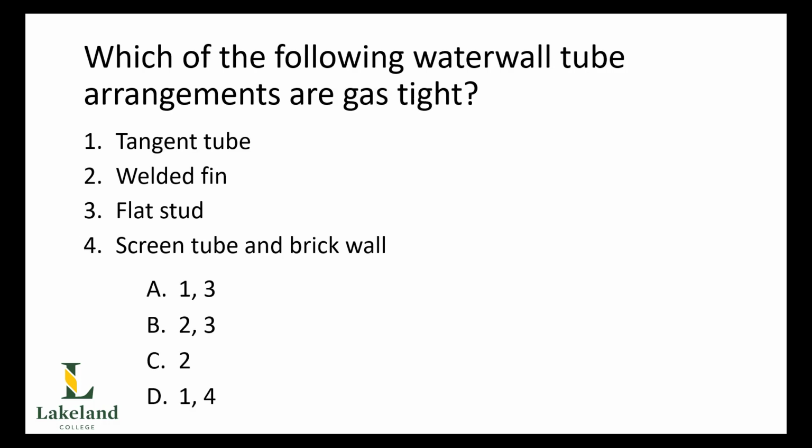Next one. Which of the following water wall tube arrangements are gas tight? We've got tangent tube, welded fin, flat stud, and screen tube and brick wall. Well, again, this is where you really need to know which one's which. Bit of a nasty question, this one, but hopefully you agree that on that list, there is only one that is gas tight, and that's the welded fin. And again, the welded fin can also be referred to as a membrane wall, and we can also get the idea of a fully studded membrane wall. The other ones here, tangent tube, flat stud, screen tube, and brick wall, they are not gas tight.